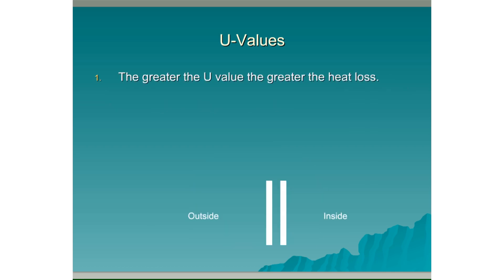The greater the U value, the greater the heat loss. Here we have an example of a standard cavity wall with an internal leaf and an external leaf. There's no insulation in the cavity, so the U value is quite high — let's say 5. Heat is generated inside the building, and because the U value is high and there's no insulation, the heat passes through the wall fairly quickly. However, if we introduce some insulation into the cavity, this can lower the U value — let's say to 1. Because the U value is lower, less heat passes through the wall.